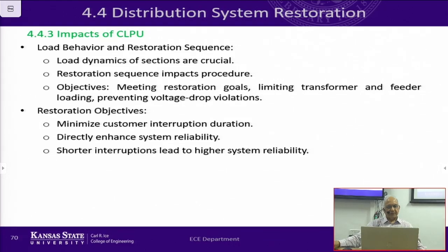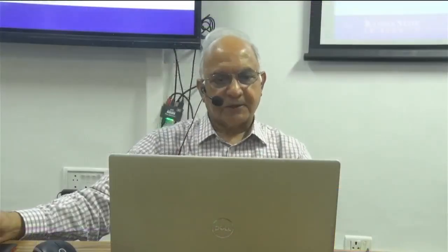And then we need to know the load dynamics, like what kind of model. Of course, I showed you the model, but how long does it remain constant, and then it starts to decrease as an exponential function. So we need to know the parameters of the model, like is it the first 10 minutes, 15 minutes, and what is the rate at which it's going to decline exponentially.